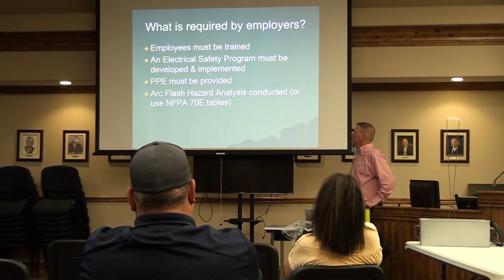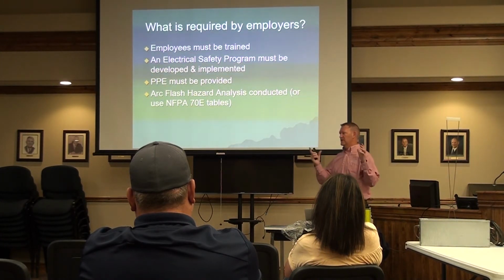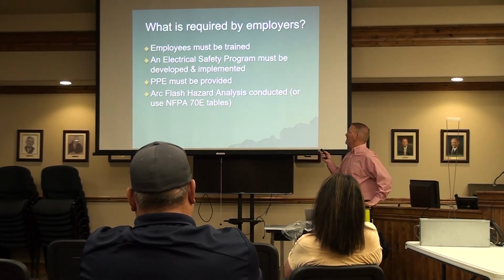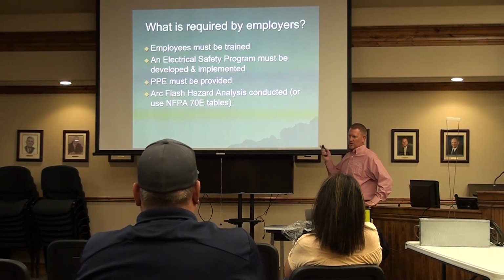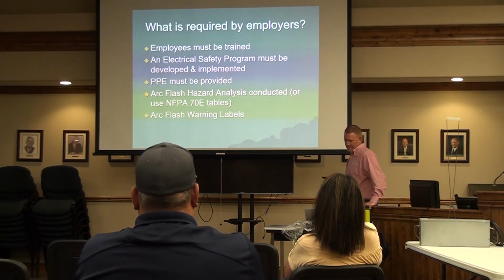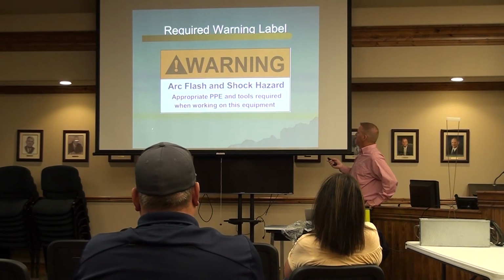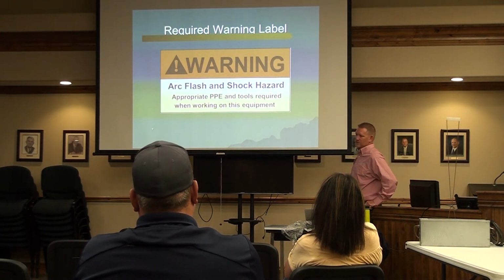Arc flash hazards analysis conducted. We've been doing this on the new facilities as they're being built. The engineering that is provided with the project. So if we build a new building in wastewater, we build new buildings in water, we actually have them put these labels on there. And these labels are what tells us what the arc flash hazards are. I'll show you one here in a minute. So this is just an arc flash shock hazard label. This is just a general, there's live parts in here.